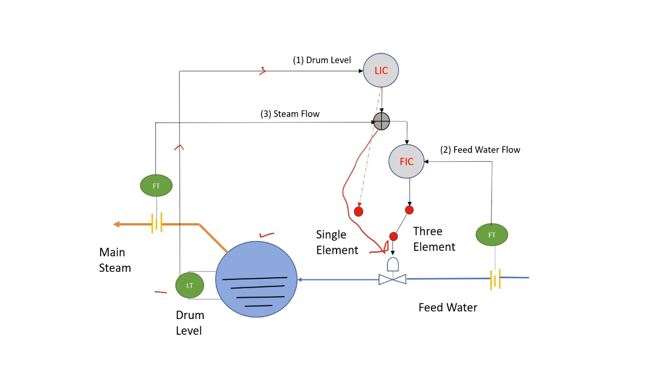This is the most simplistic form of the control scheme and this is single element control, where drum level is the only element that is being measured and the feed water flow rate is controlled to maintain the drum level.